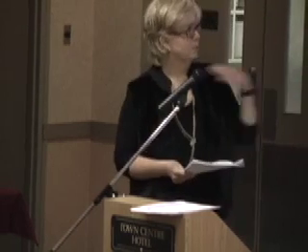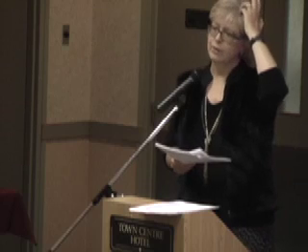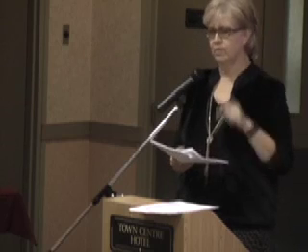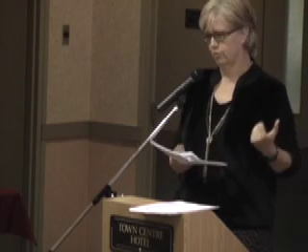This particular slide, which might be quite hard to see, talks a little bit about outage. Today, we don't know if you're out. With smart meters, they have a battery power pack on them. When the power is out, that meter sends a signal to a control center down in the Lower Mainland. We call it the last gasp signal, and it tells us that it's out. If we see just one meter out, we know you're probably doing some construction. But if we see a bunch of meters starting to go out, we know that there's an outage.